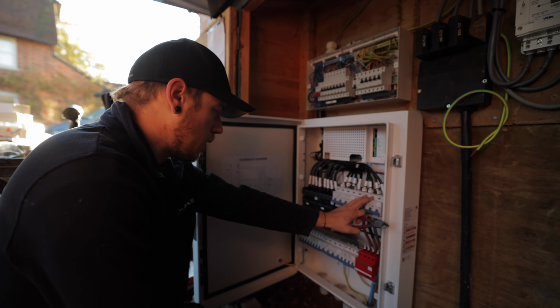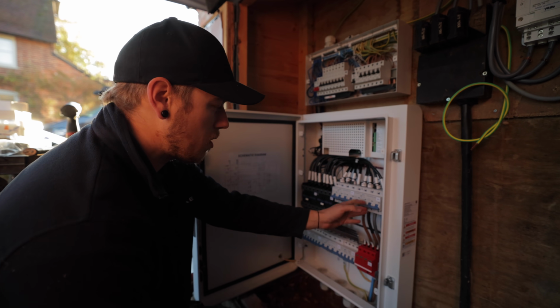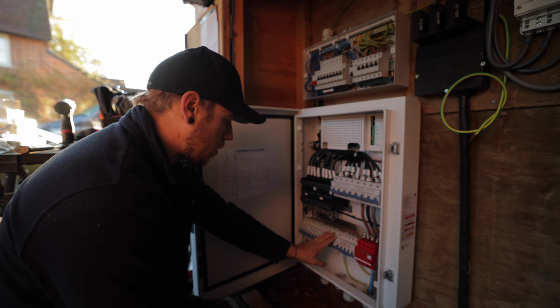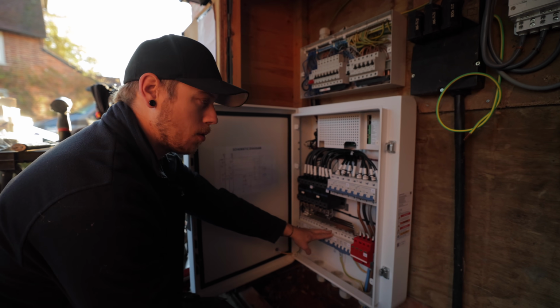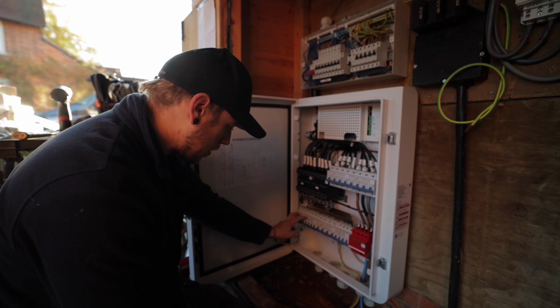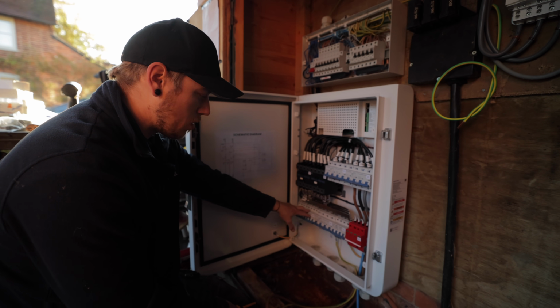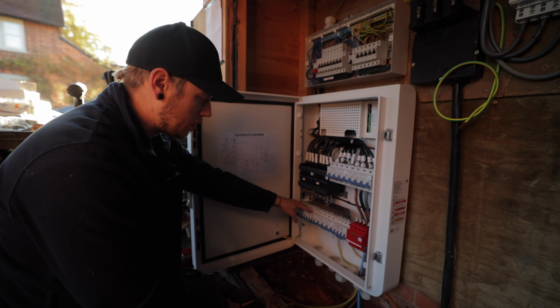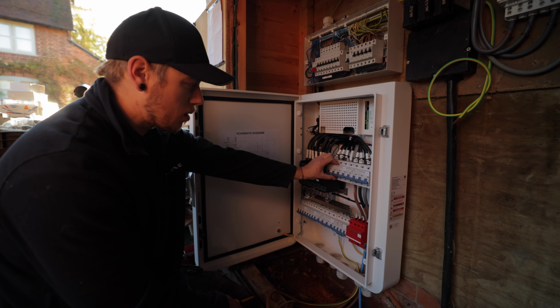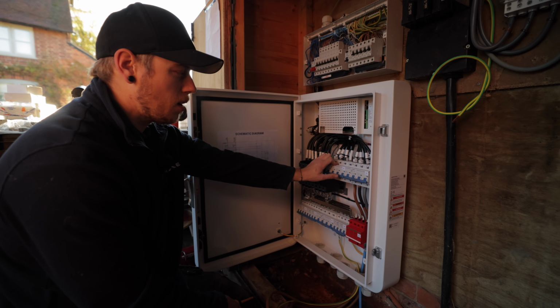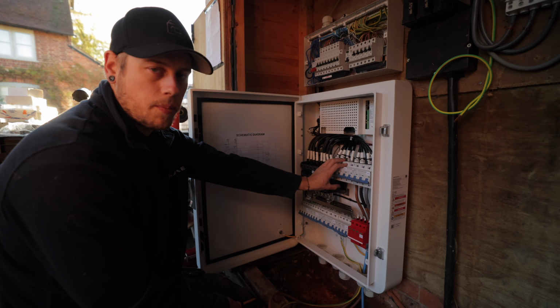The tails are away into the grid switch now. Basically you've got your feed coming in from your meter, and this one down here is your feed back out, so that goes to the Henley blocks. These two are inverter 1 and inverter 2, which do both our stacks of batteries. And this one up here is the smart port, for anything you don't want on the backup side.